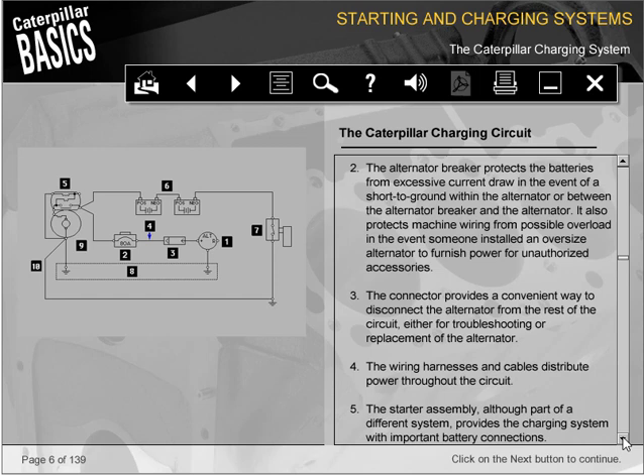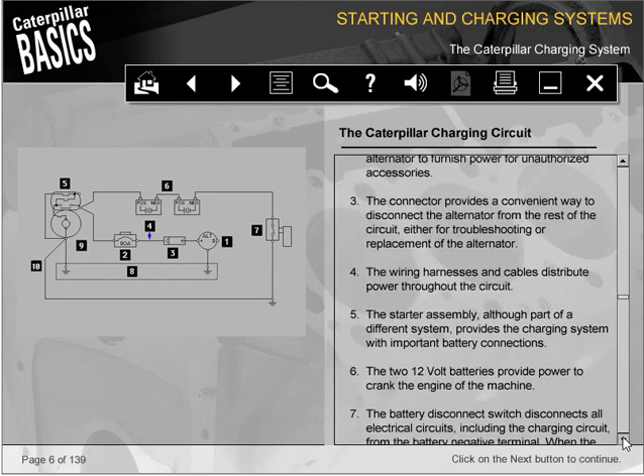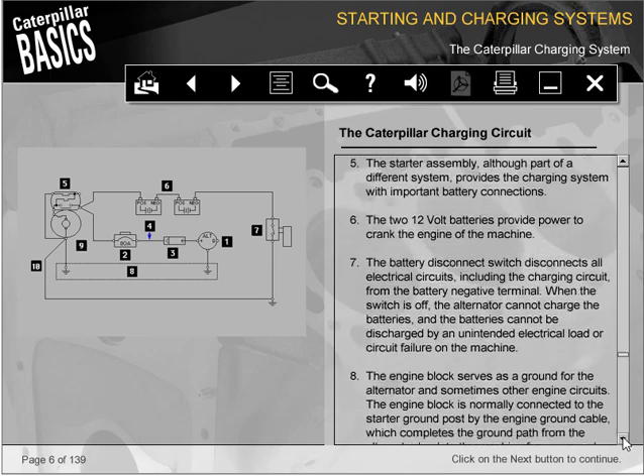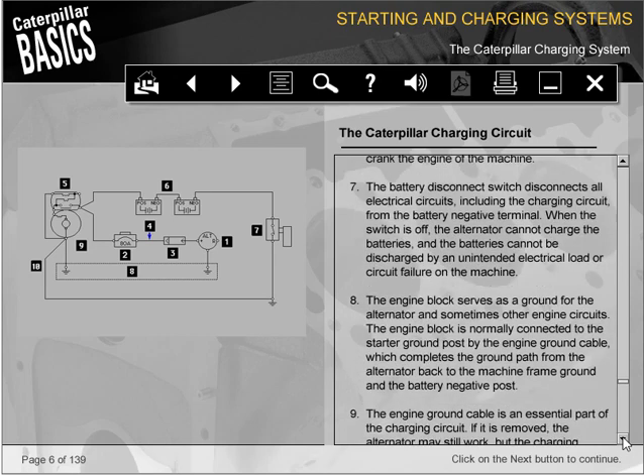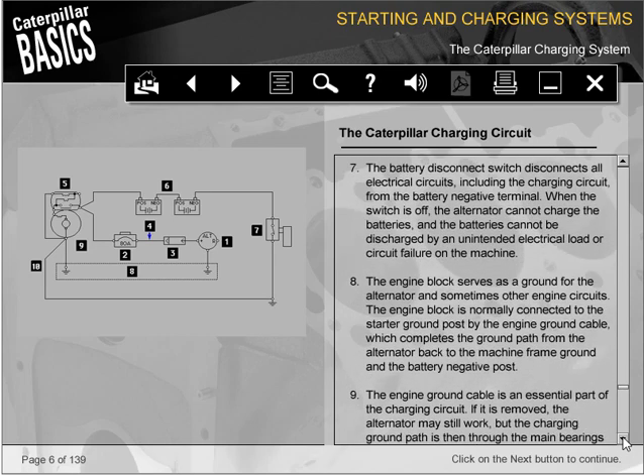6. The two 12-volt batteries provide power to crank the engine of the machine. 7. The battery disconnect switch disconnects all electrical circuits, including the charging circuit, from the battery negative terminal. When the switch is off, the alternator cannot charge the batteries, and the batteries cannot be discharged by an unintended electrical load or circuit failure on the machine.